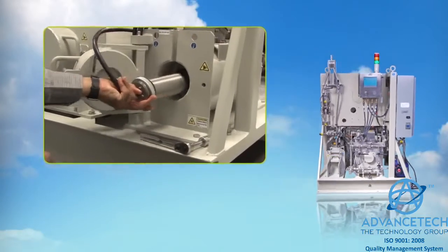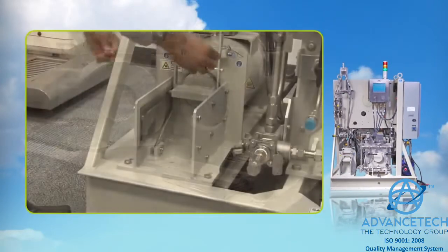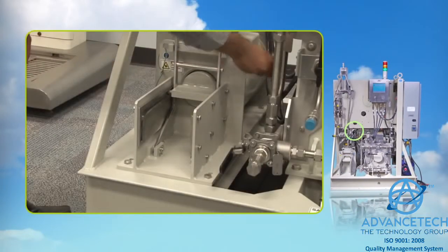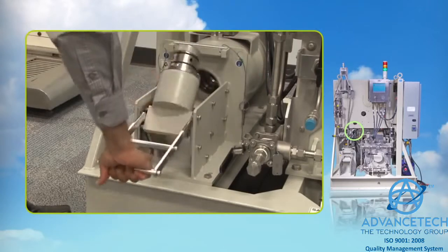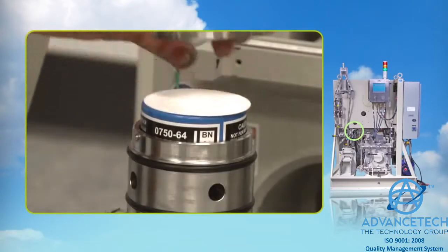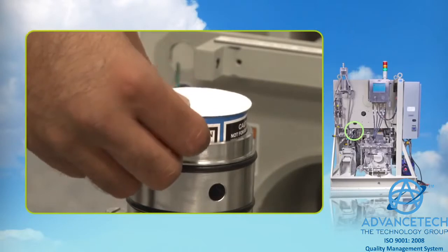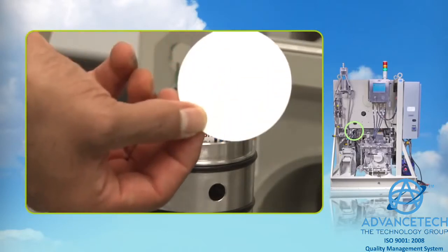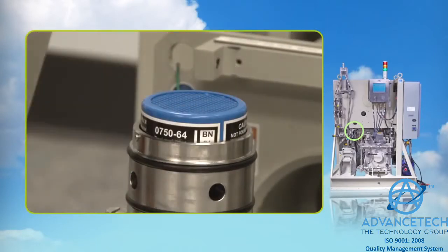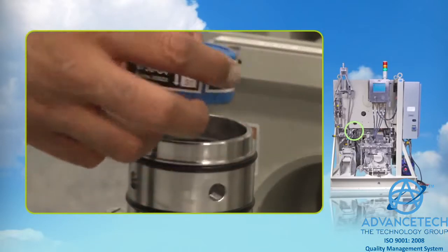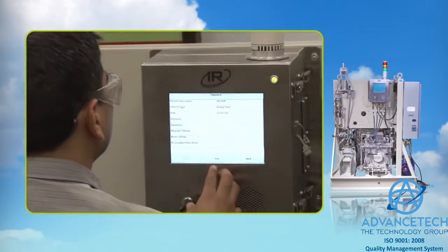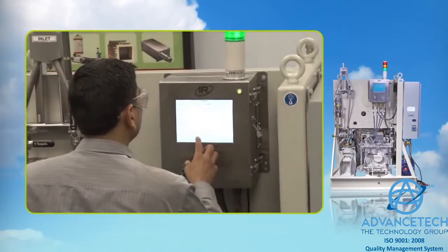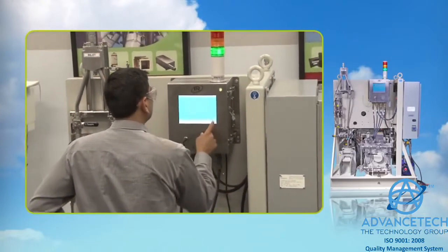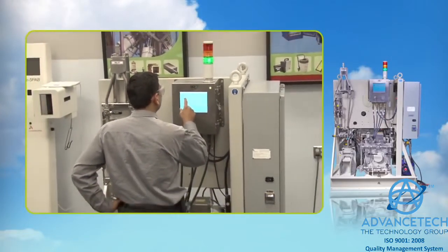Where a shielded sampler is employed for the normal flow path, a differential pressure sensor is provided across the filter paper and charcoal cartridge. The sensor detects changes in the differential pressure that occur when the filter starts to clog. The sensor feeds to the rate meter, which can be set to alarm for a filter replacement based on pre-selected alarm set points. This functionality can offer several benefits.